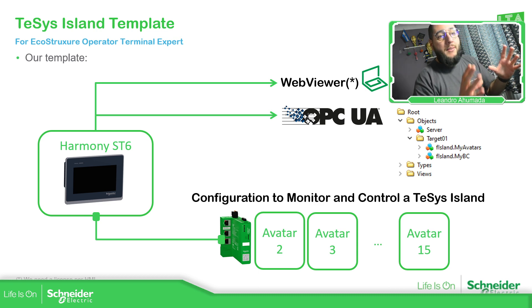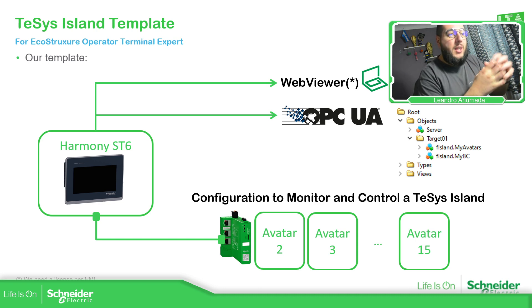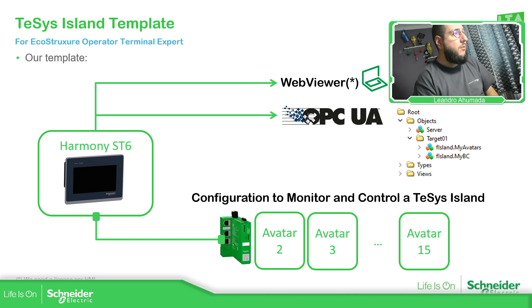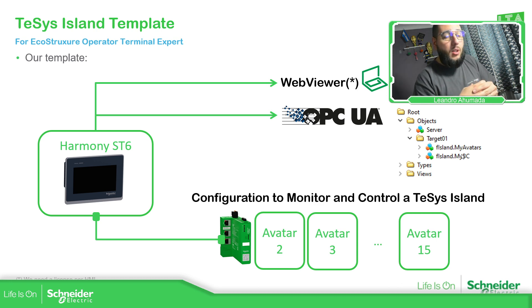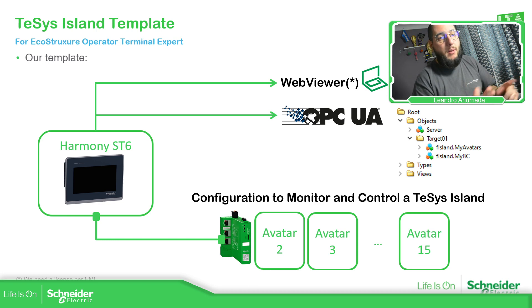One of the features of this HMI is OPC UA. All the variables and readings from the HMI are available on OPC UA, so the HMI is an OPC UA server. You can use any client to access the arrays of avatars and their information. We also have the possibility to use the web viewer — to see the HMI application on your smartphone, tablet, or computer — which just requires a license, but it isn't that expensive.